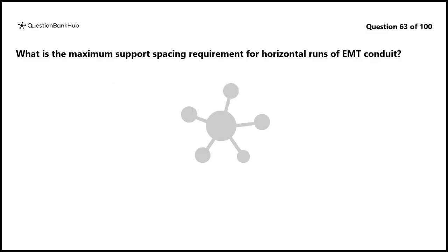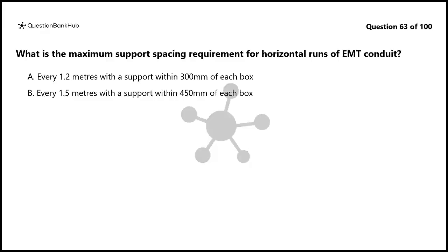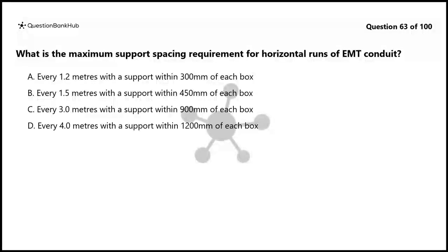Question 63. What is the maximum support spacing requirement for horizontal runs of EMT conduit? A. Every 1.2 meters with a support within 300 millimeters of each box. B. Every 1.5 meters with a support within 450 millimeters of each box. C. Every 3.0 meters with a support within 900 millimeters of each box. D. Every 4.0 meters with a support within 1,200 millimeters of each box.